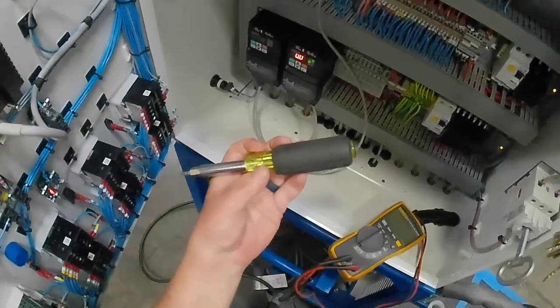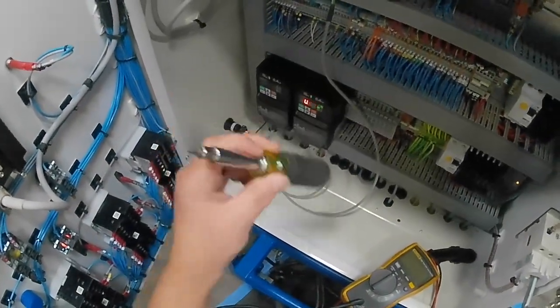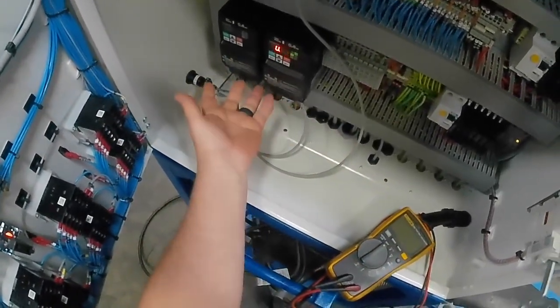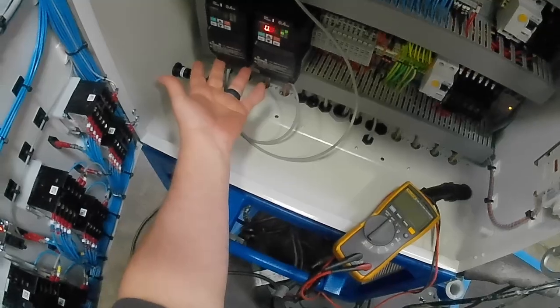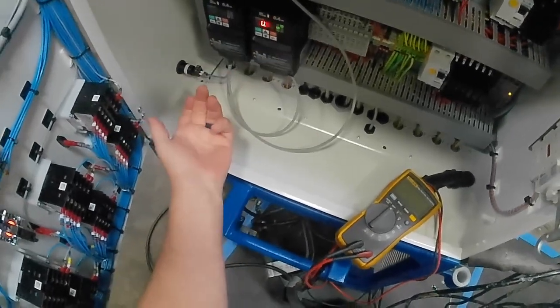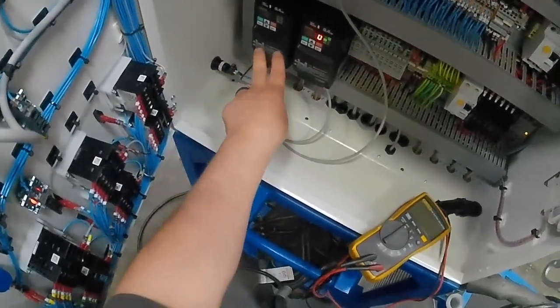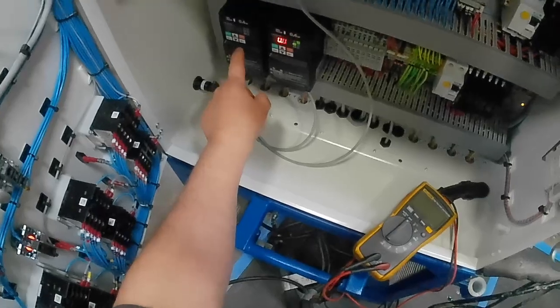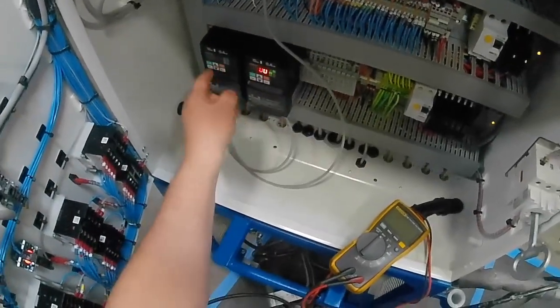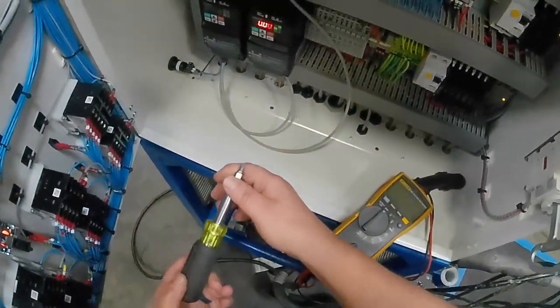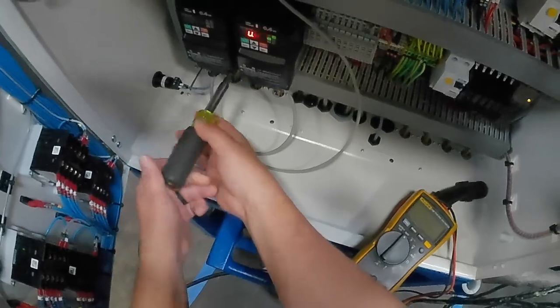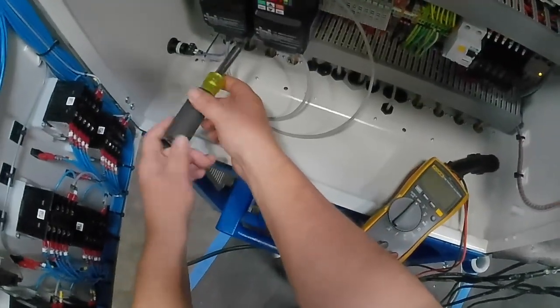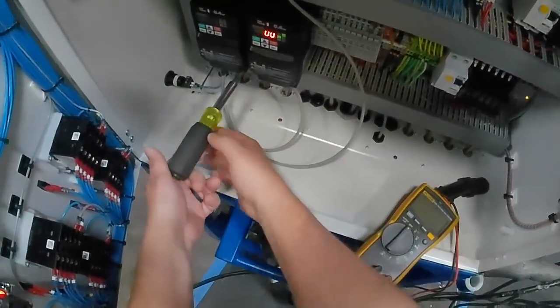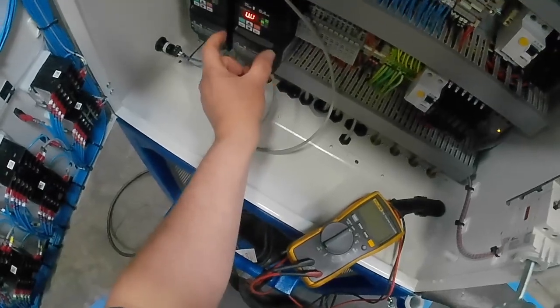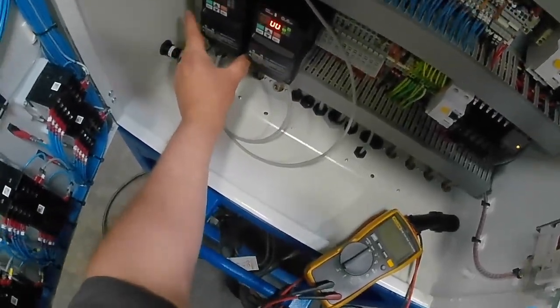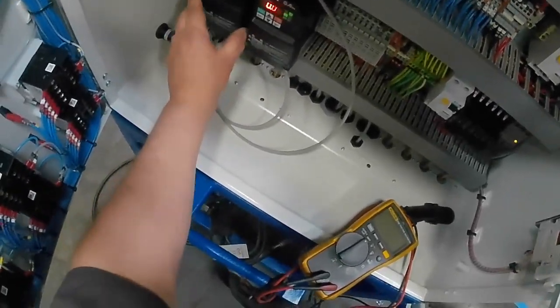Okay boys, we're back, and I went and got my 11-in-1 screwdriver. So I'm gonna go ahead and take the cover guard paneling off of this, and let's open this up, and I'm gonna try to find my supply side wiring for this inverter and see what kind of power we have running to it, and we'll see what's going on with it. So I'll open up this one and try to pull the cover off. I think these Hitachis have two covers. One is for the control inputs and one is for the power wiring, which is at the bottom.